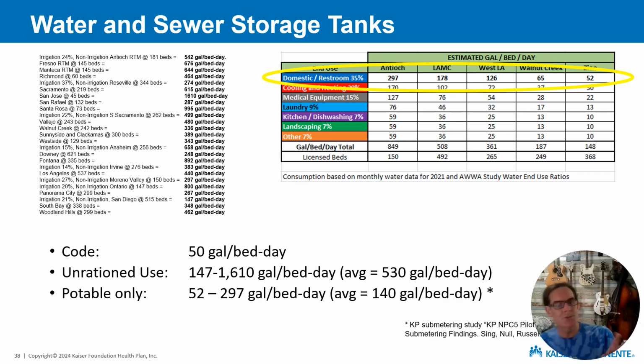We've also done some sub-metering studies to try to figure out the actual consumption of the potable only, and that came out to between 52 gallons per bed per day and 300 gallons per bed per day, the average there being about 140. Suffice to say that in 99 out of 100 cases, 50 gallons per bed per day, the way the code is sizing, is not going to get you anywhere near 72 hours. If you were to actually lose water in an event, which is an extremely unlikely event, you would only last a few hours based on the tank sizing that we have.